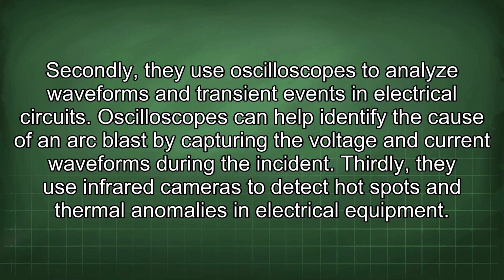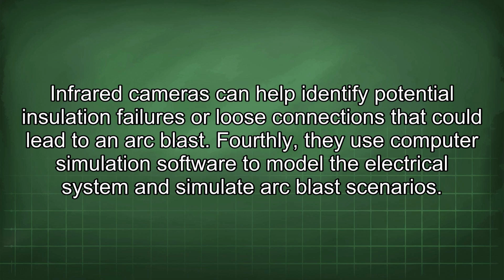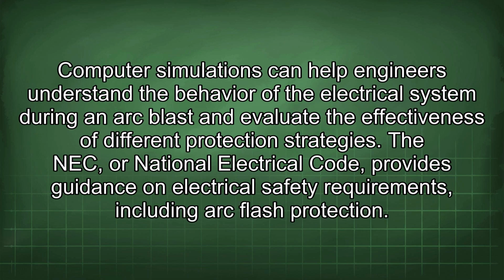Oscilloscopes can help identify the cause of an arc blast by capturing the voltage and current waveforms during the incident. Thirdly, they use infrared cameras to detect hotspots and thermal anomalies in electrical equipment. Infrared cameras can help identify potential insulation failures or loose connections that could lead to an arc blast. Fourthly, they use computer simulation software to model the electrical system and simulate arc blast scenarios.